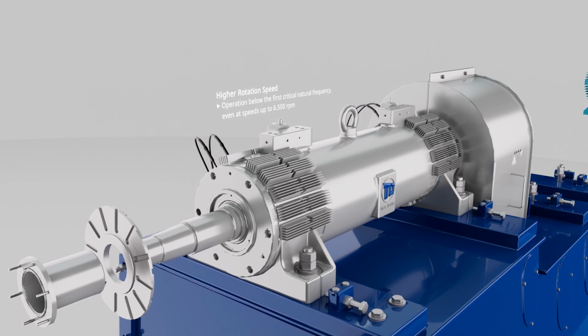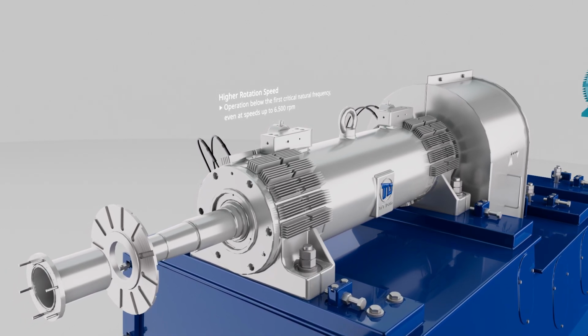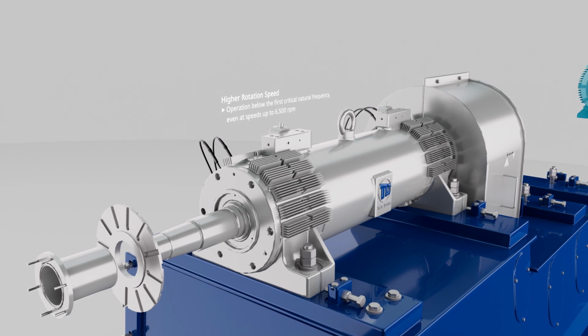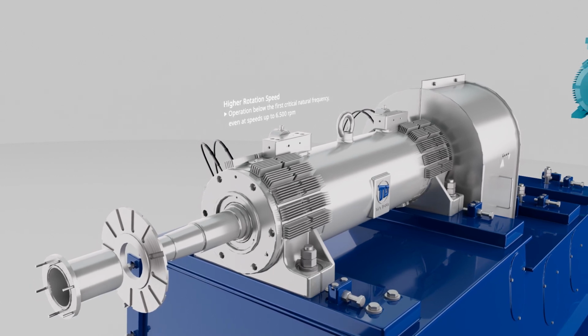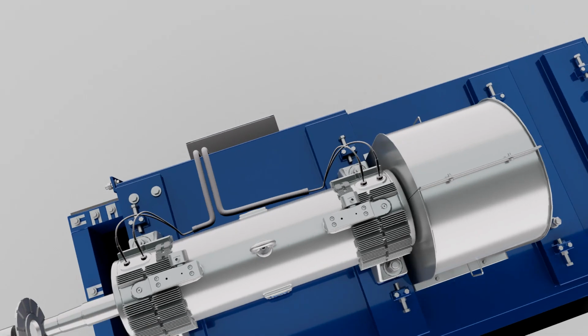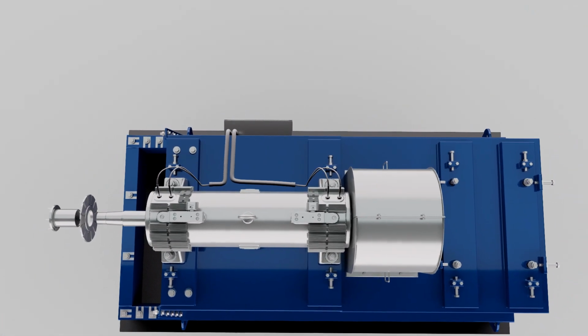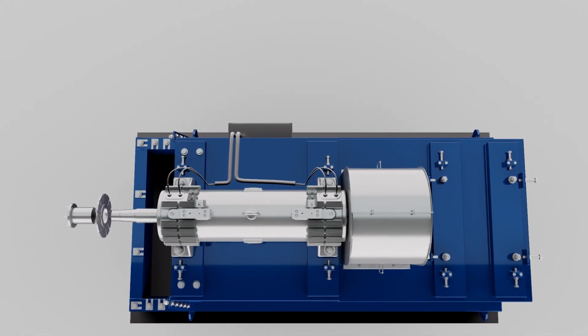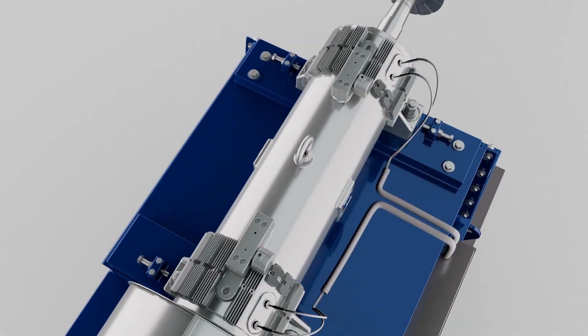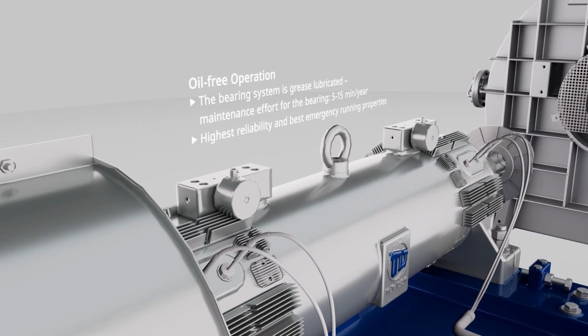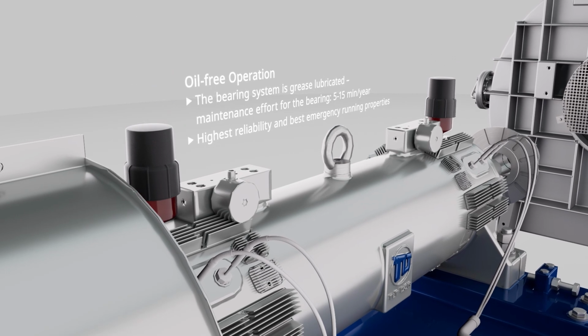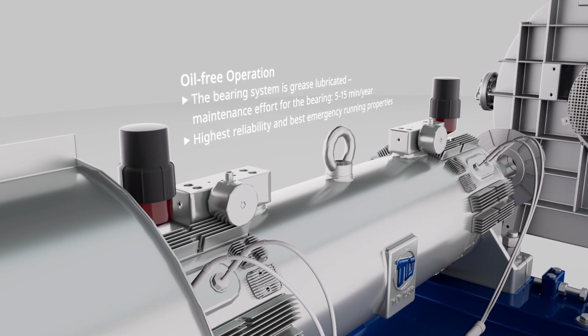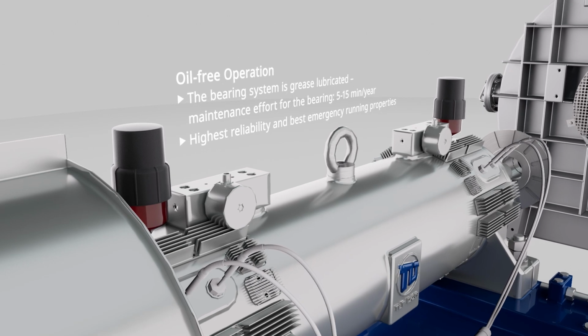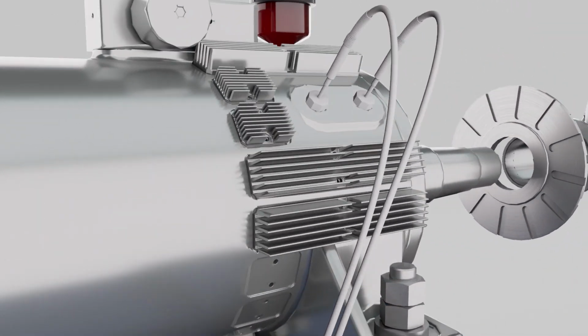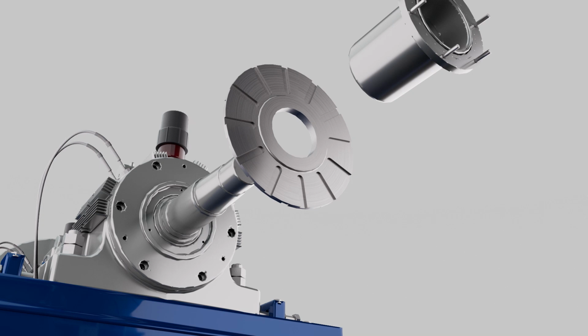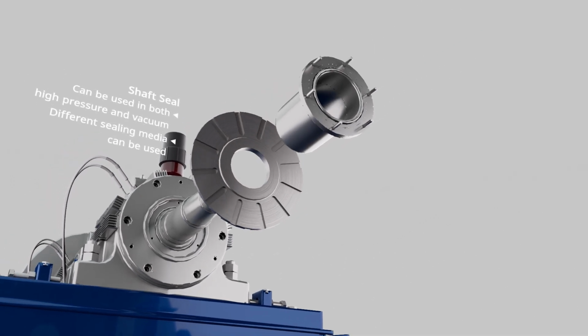This has made dampening in the bearing superfluous. There's no need for an oil system at all. The bearing is lubricated with grease and requires very little maintenance. The bearing systems have a service life of at least 10 years, and this can be notably extended by the application of an automatic grease cartridge, which is easy to install every few years. To cool the bearing, TLT Turbo uses a passive cooling system comprised of a cooling disc on the shaft and, if necessary, additional cooling fins on the bearing housing.